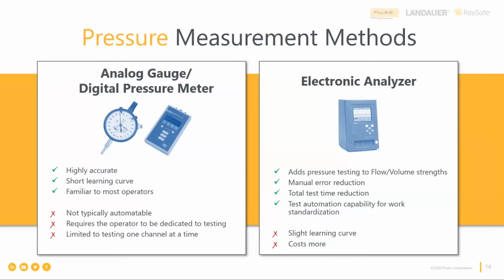Again, both have pros and cons to them. The analog gauge or the digital pressure meter that you could use, they will be accurate. I mean, there will be a short learning curve to it, if any at all, because they're familiar to most operators. However, they are not automatable. So there will be some time waste there. They will require the operator to be dedicated to testing because the operator needs to be there to record the parameters. And of course, they're limited to testing one infusion channel at a time, which is mitigated by using electronic analyzers, especially the multi-channel ones, when measuring pressure of the infusion pump.